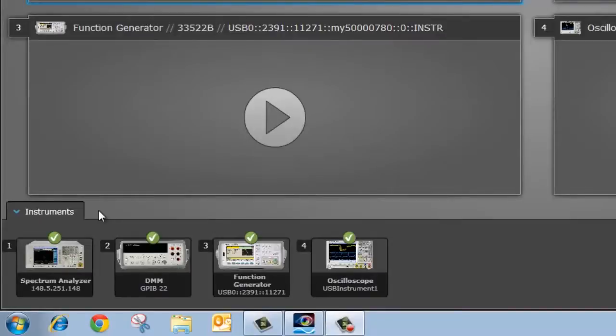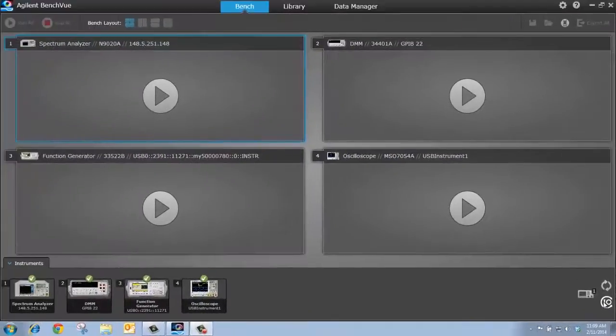Now, BenchVue will automatically detect and connect to instruments through GPIB and USB. For LAN and RS-232, you need to manually configure those instruments using a VISA configurator that you can access through this IO icon. Once you configure the instrument, it'll always show up in the future when you open BenchVue. For more information, see the tutorial connecting your instruments to BenchVue.